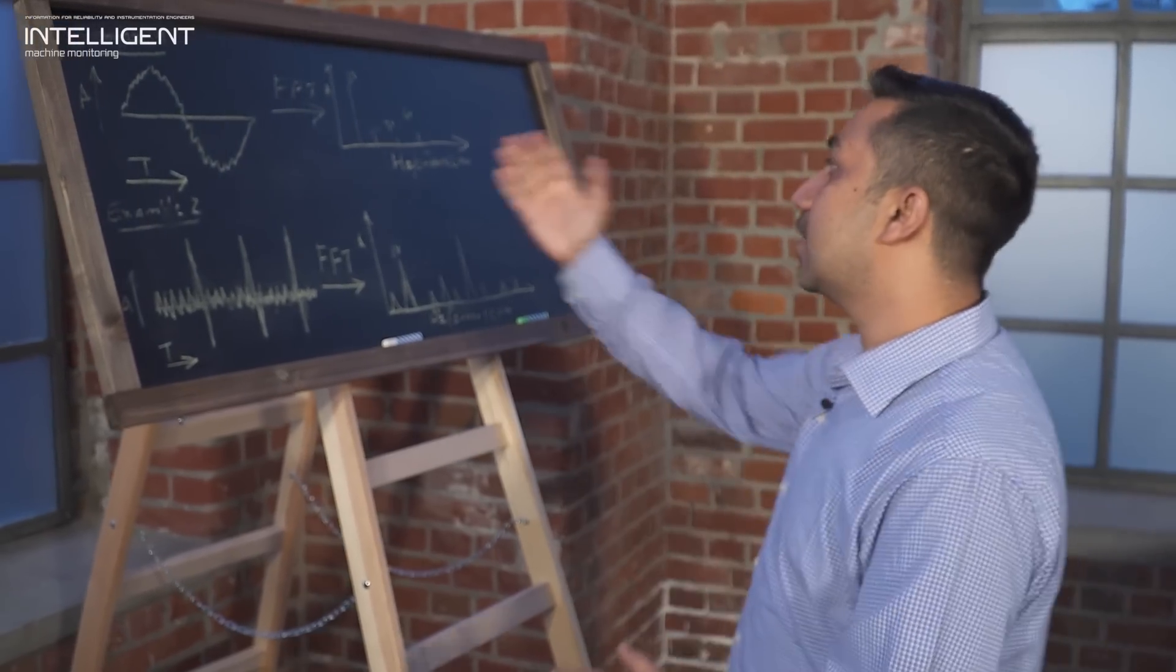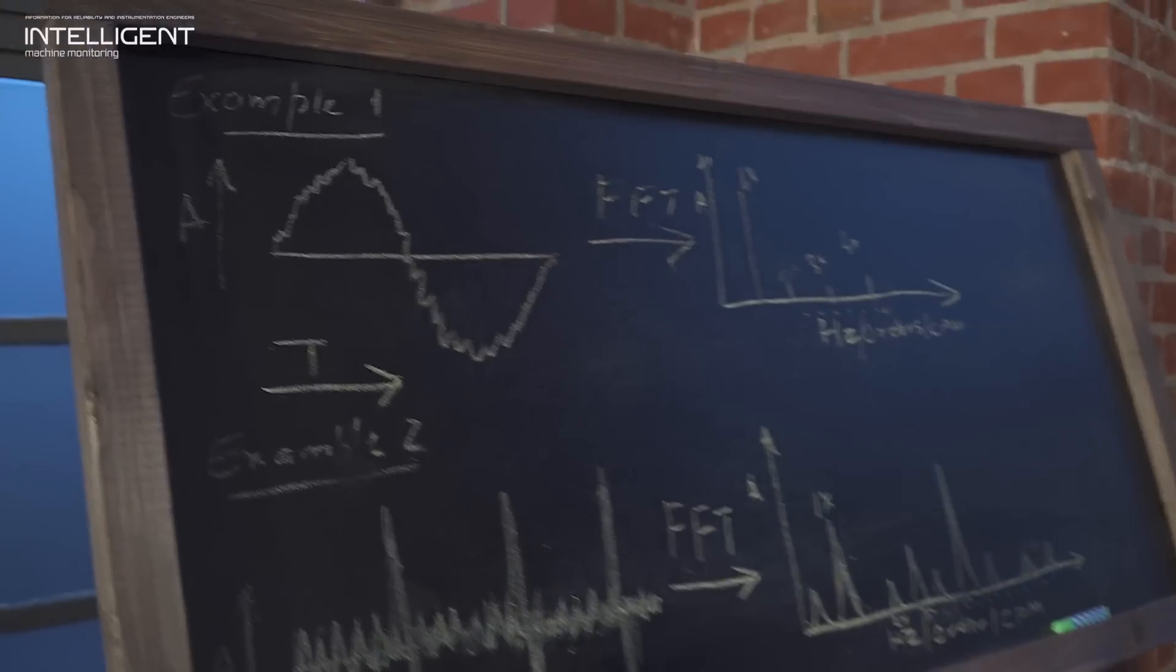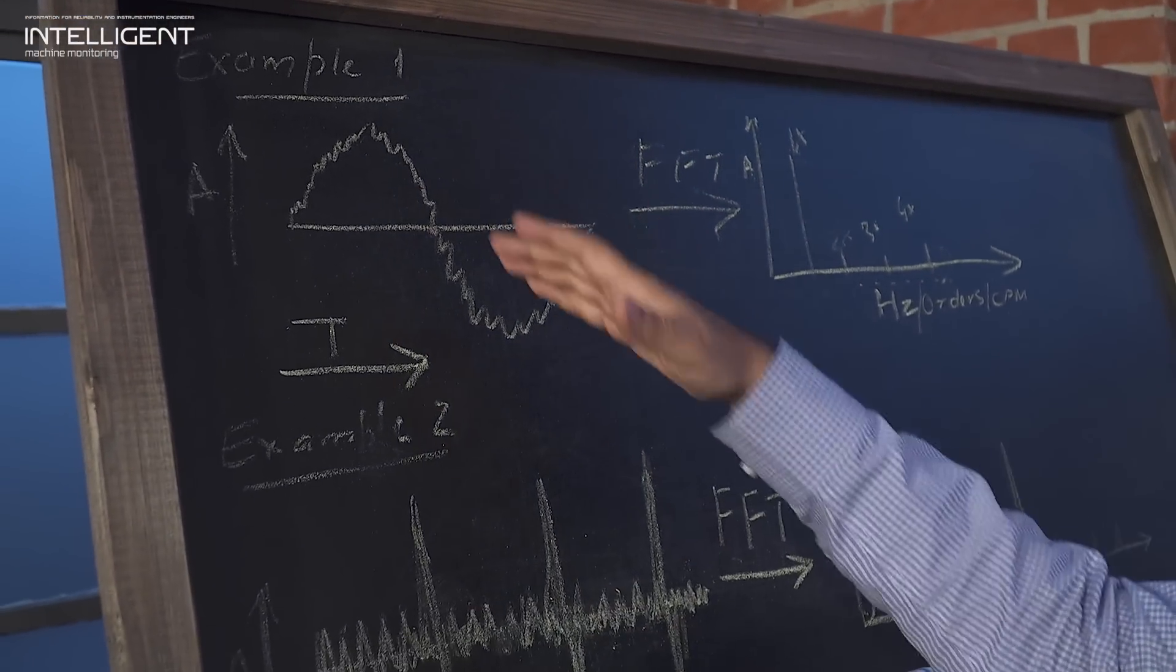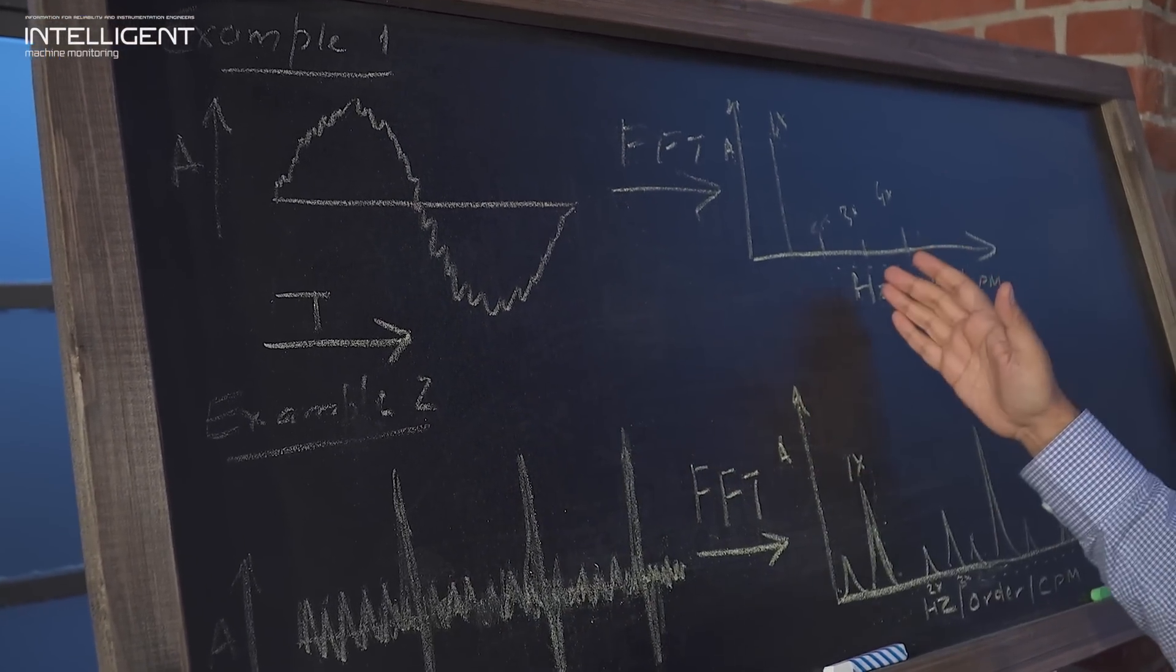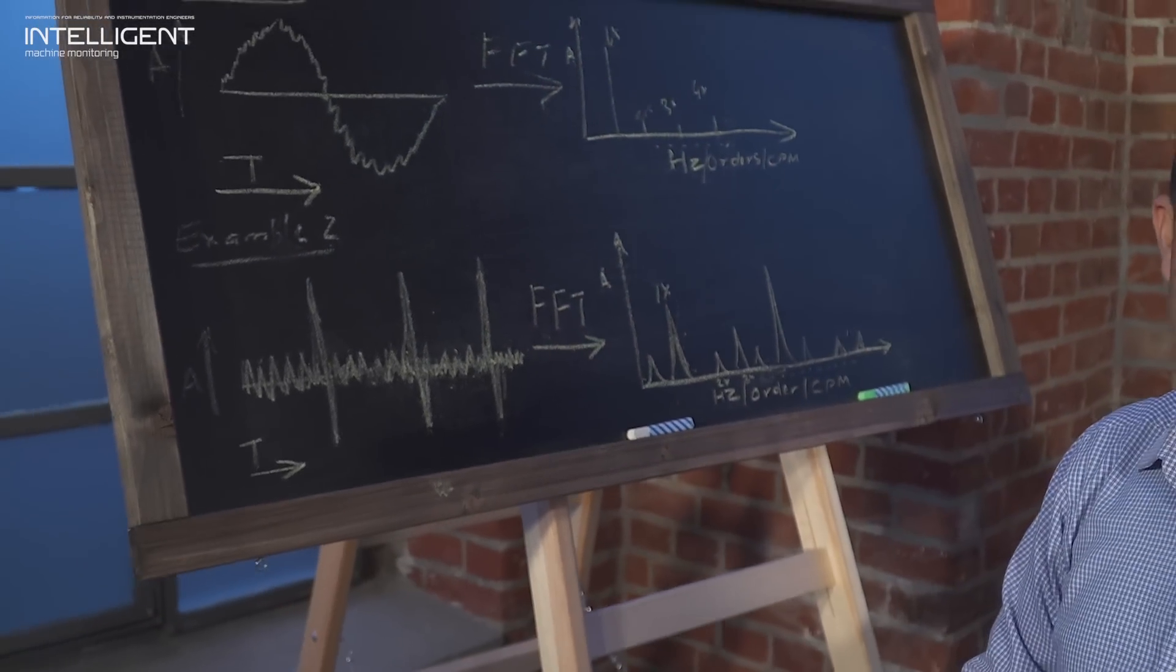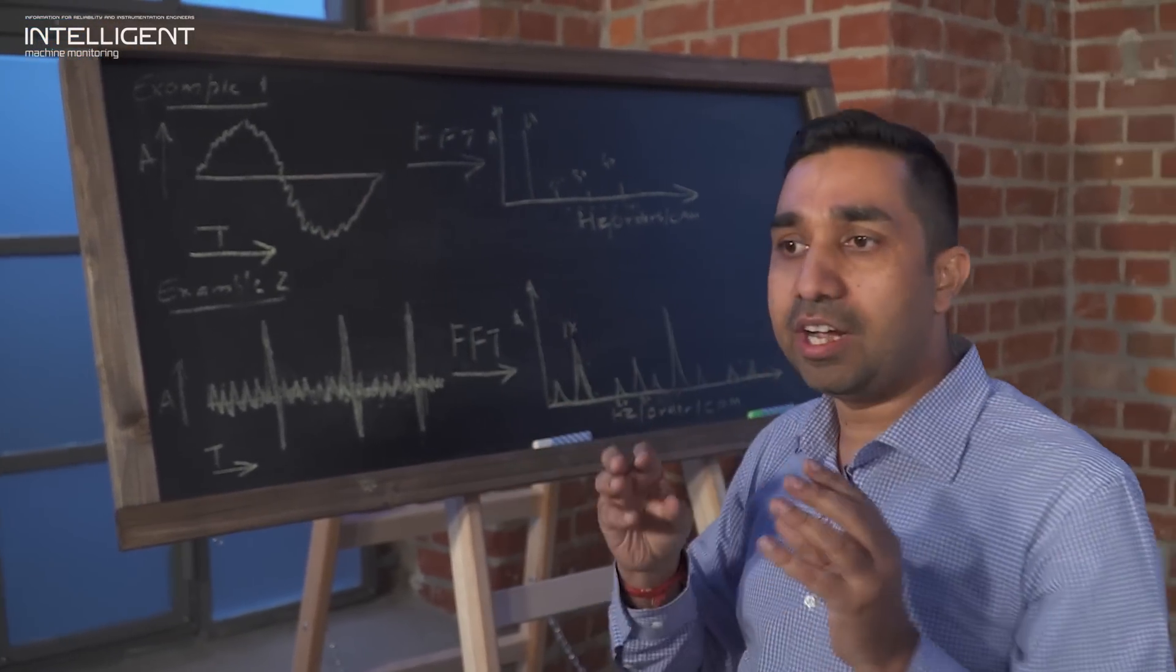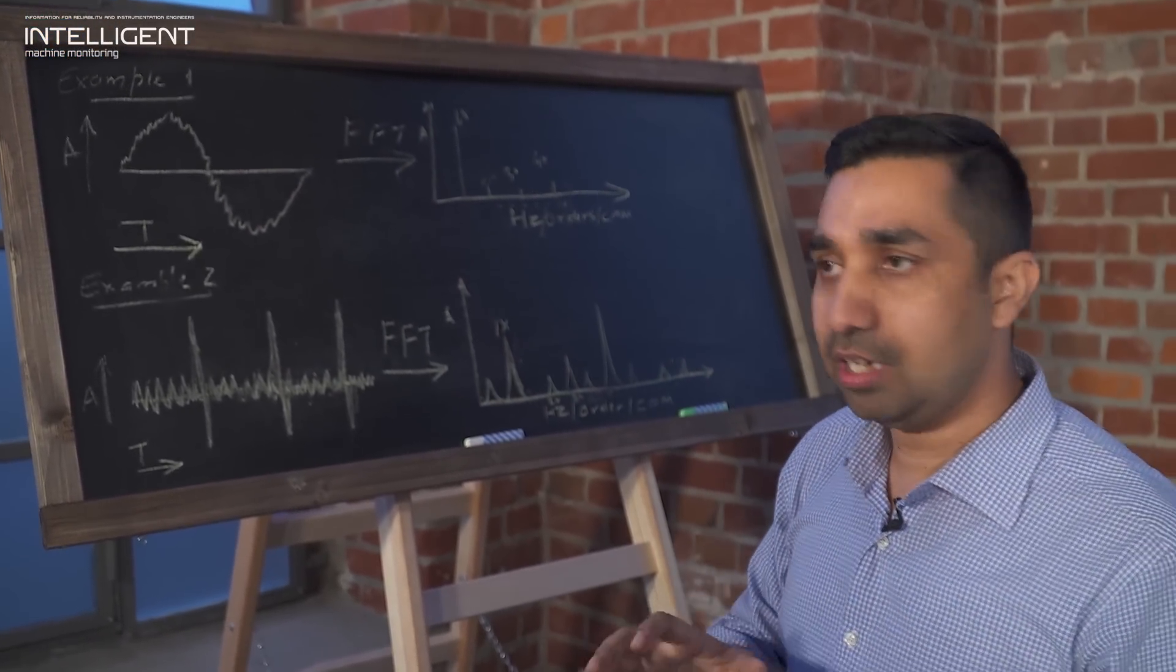To validate this statement, I will take two examples. The first example is a machine that is out of balance. The time signal looks very sinusoidal and FFT has a dominant 1x turning speed frequency. In this case, both these plots give you a hint of unbalance.